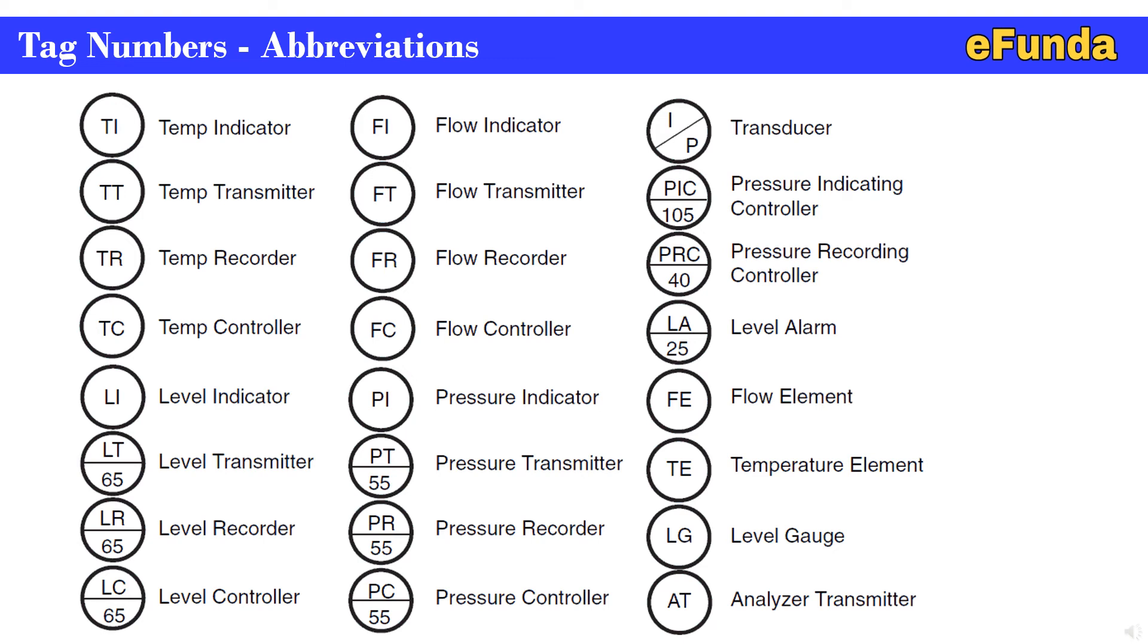Similarly, in the miscellaneous column, one can see I2P, that is a transducer. PIC is pressure indicating controller, PRC is pressure recording controller. LA is level alarm, FE is flow element, TE is temperature element, LG is level gauge, AT is analyzer transmitter. This is how the nomenclature or abbreviation for the tags are indicated on the P&ID.